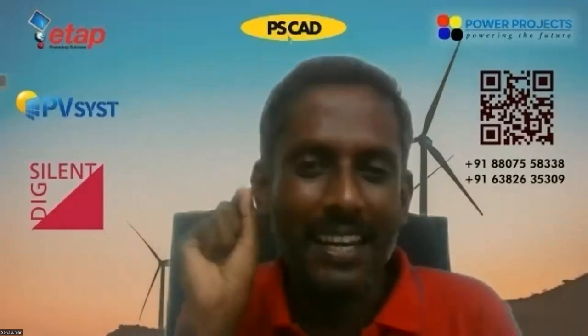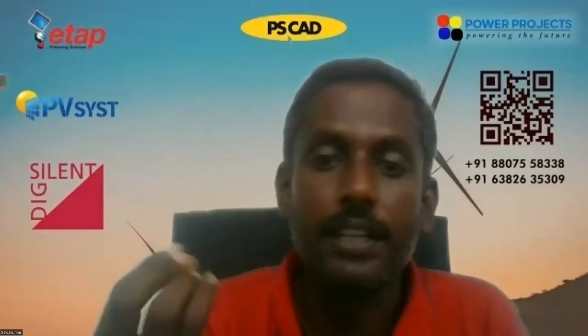Short circuit study and relay coordination study are your responsibility if you are performing an arc flash study. You cannot recommend instantaneous protection just to reduce the PPE requirements or incident energy. Safety is important, but at the same time, protection coordination is also important. Losing production in the industry, with the incomer tripping just for a fault in one of the outgoing feeders, is nowhere logical. And these people will understand only when a fault happens and the incomer trips. Then they will find another consultant and ask what the issue is, to find it out. So you need to be very, very careful, and it's our responsibility.